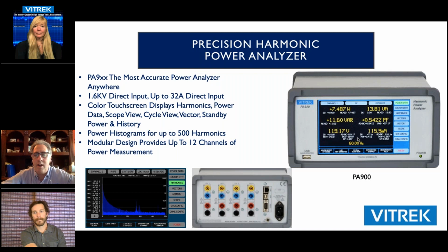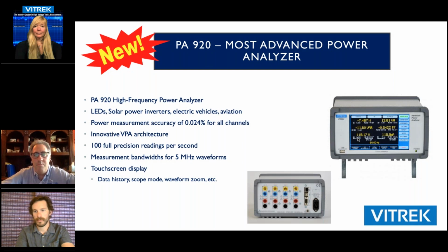The second product is our harmonic analyzer, power analyzer. This is key when looking at the energy consumption of products, both in the lab when building new products and testing how much energy is used, the volts, amps, power factor, and harmonics. It accumulates all the data, which we can graph in a histograph or vector diagram. We can also run standby power tests to make sure it's not consuming too much. It's a solid tool for both the laboratory and the production floor, and even gets integrated into some products themselves. Even though this product was already extremely accurate, we recently came out with a new one in the fourth quarter of 2019 called the PA 920.